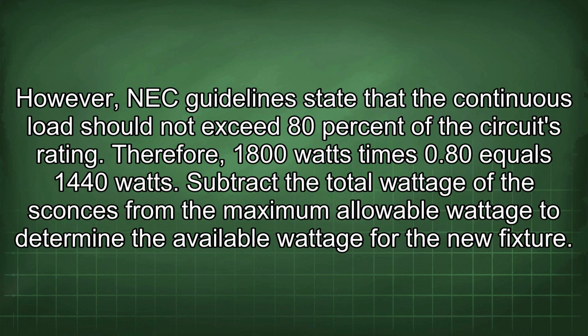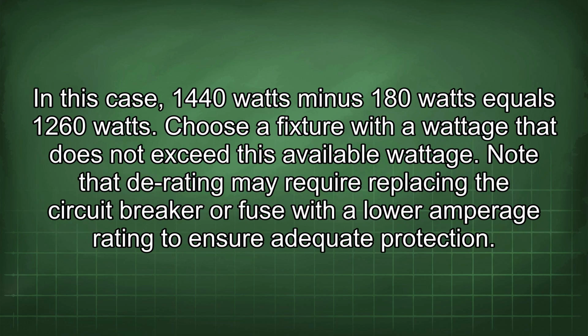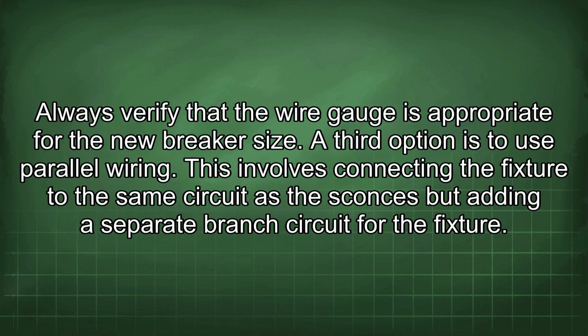However, NEC guidelines state that the continuous load should not exceed 80% of the circuit's rating. Therefore, 1800 watts times 0.80 equals 1440 watts. Subtract the total wattage of the sconces from the maximum allowable wattage to determine the available wattage for the new fixture. In this case, 1440 watts minus 180 watts equals 1260 watts. Choose a fixture with a wattage that does not exceed this available wattage. Note that de-rating may require replacing the circuit breaker or fuse with a lower amperage rating to ensure adequate protection. Always verify that the wire gauge is appropriate for the new breaker size.